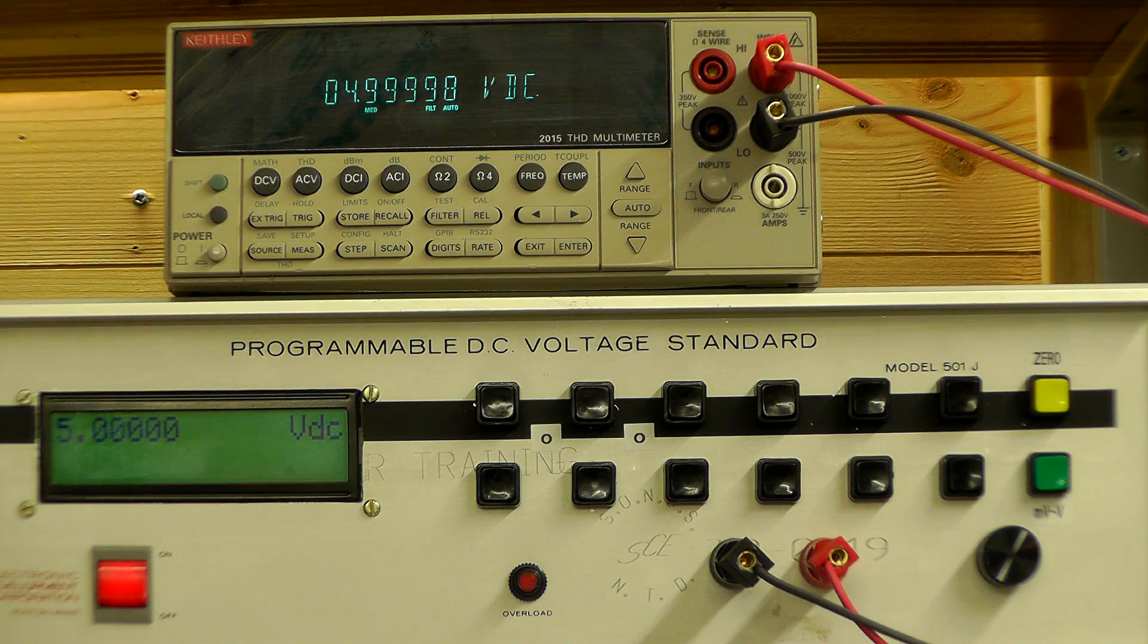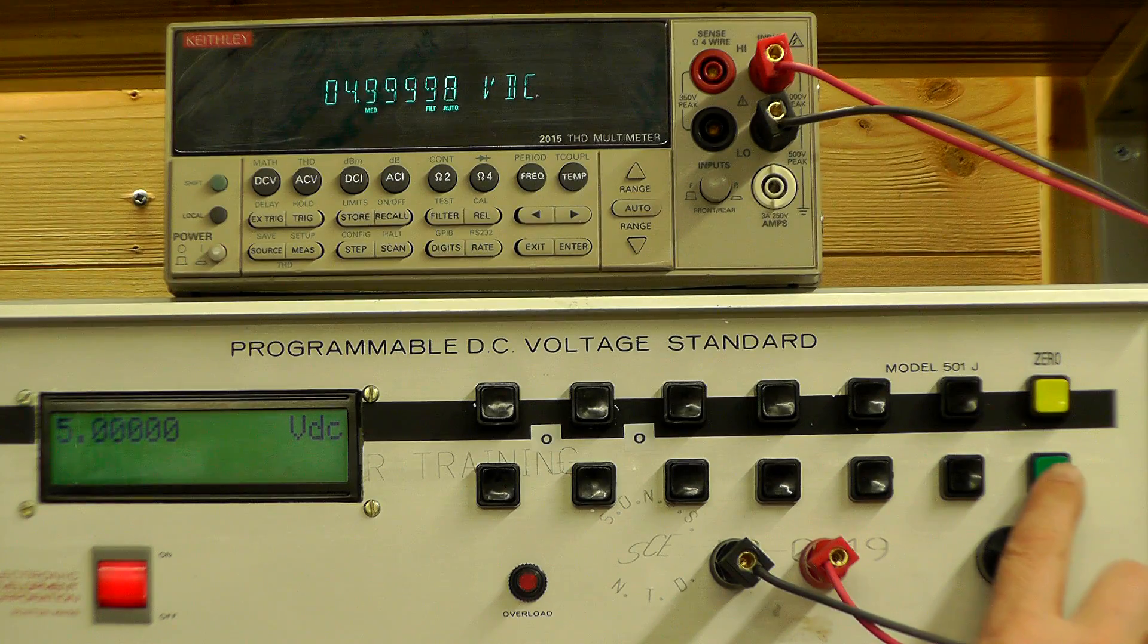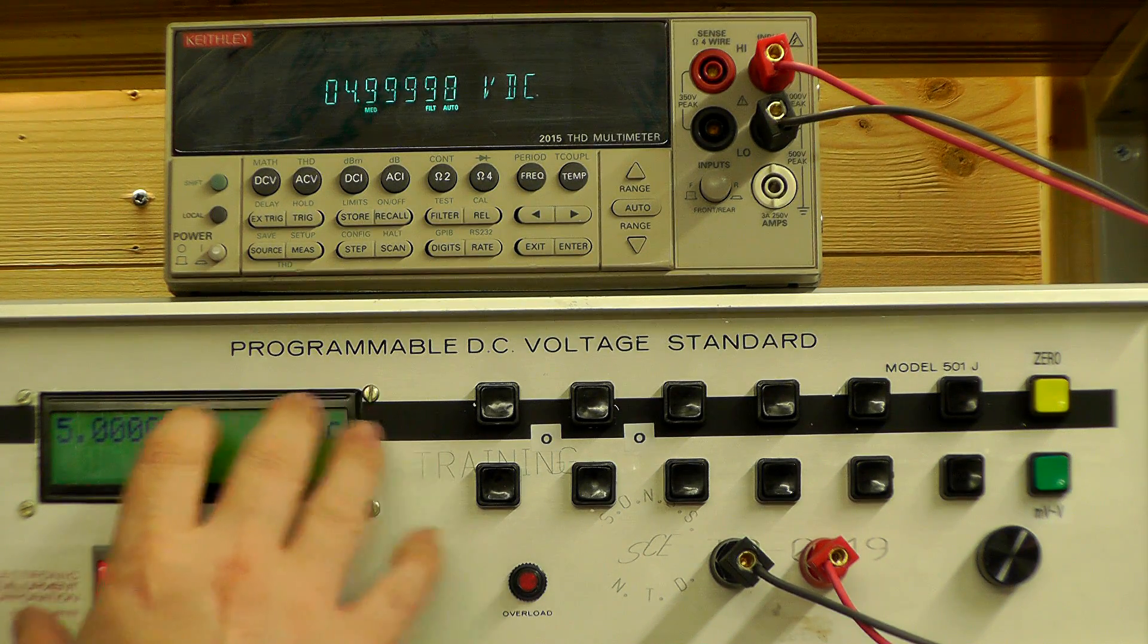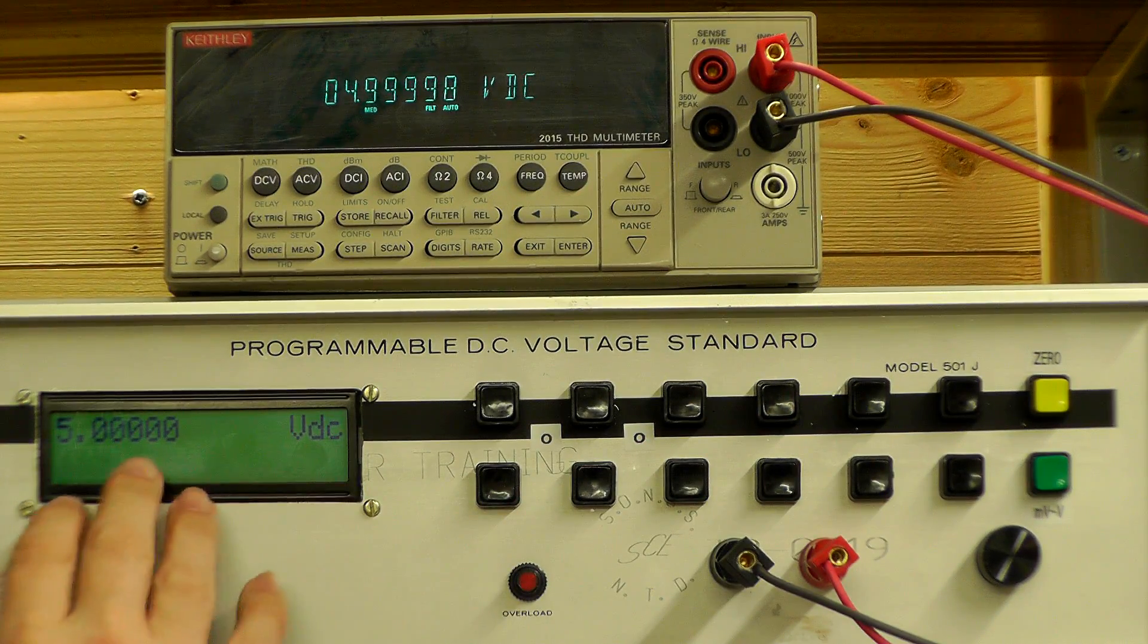Which is about 30 microvolts out at the moment. So if I push the millivolt-volt push button, this is a momentary push button and basically it will cycle the display around 4 different modes that I've got the software configured for. So mode 1 is going to give me the voltage output from the push buttons.